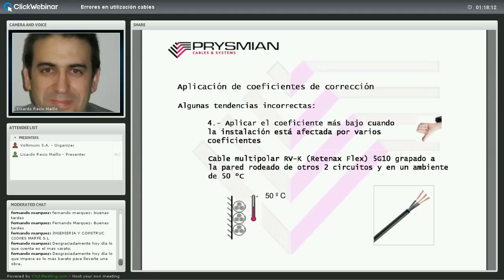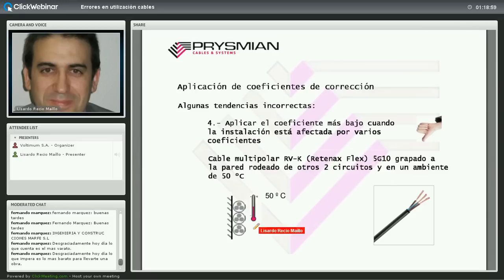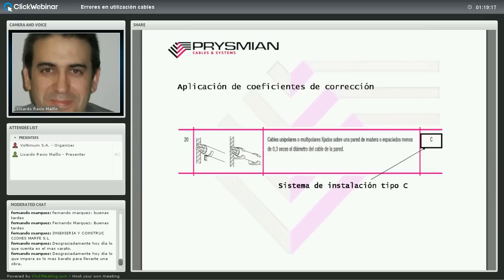Ejemplo de cálculo con coeficientes de corrección: cable multipolar tipo Retenax Flex RV-K 0,6/1 kV, 5G10, grapado a la pared, rodeado de otros dos circuitos en contacto, temperatura ambiente 50 °C. El sistema de instalación es C (cables fijados en pared). Entramos en la tabla por sistema C, columna XLPE3 (trifásico, termoestable), sección 10 mm²: la tabla nos da 60 A. Pero esas condiciones estándar son sin circuitos alrededor y a 40 °C, por lo que debemos aplicar coeficientes de corrección.